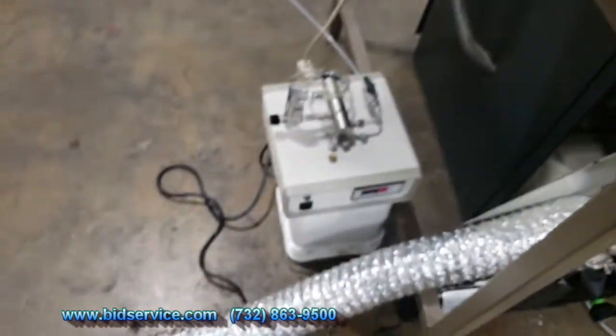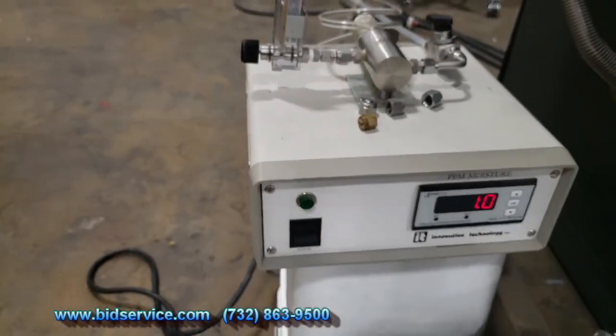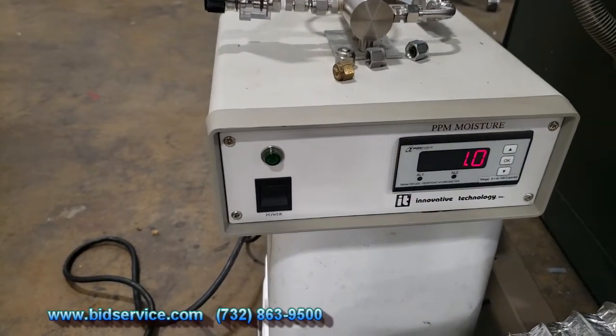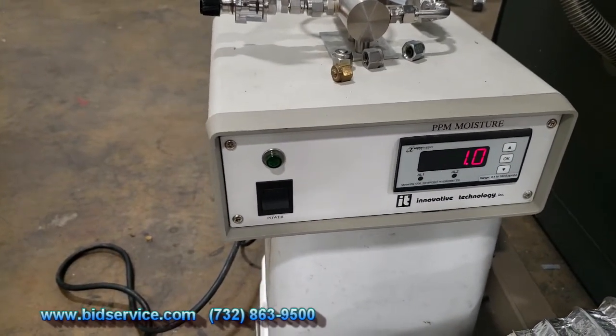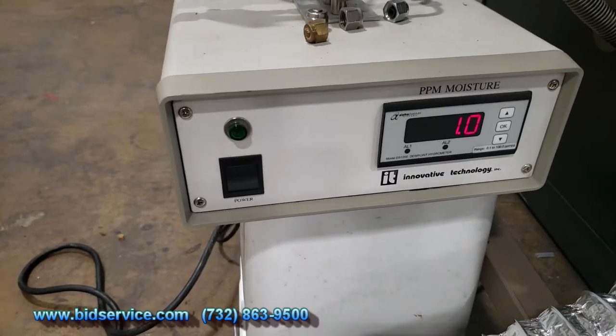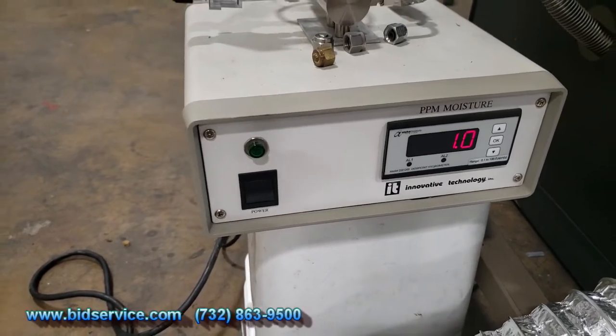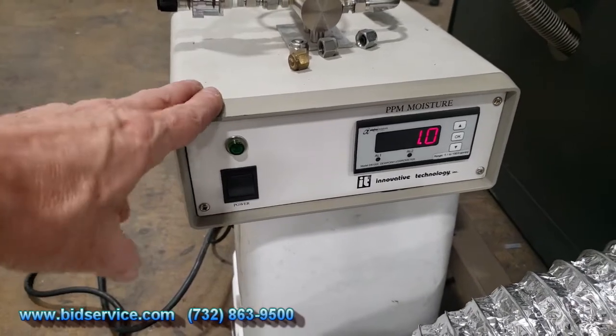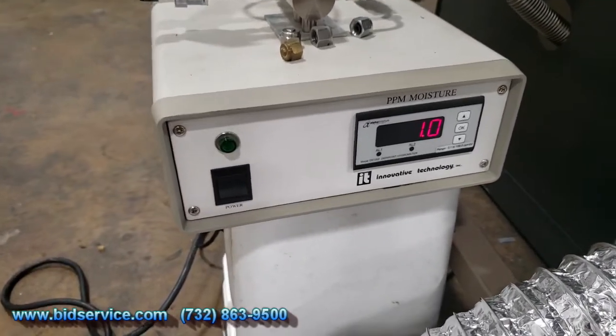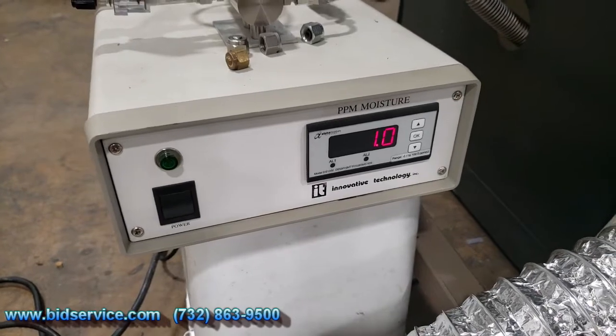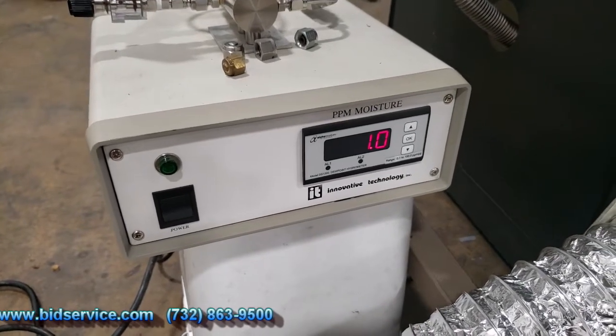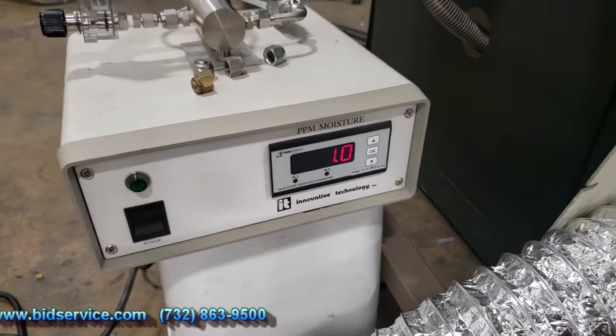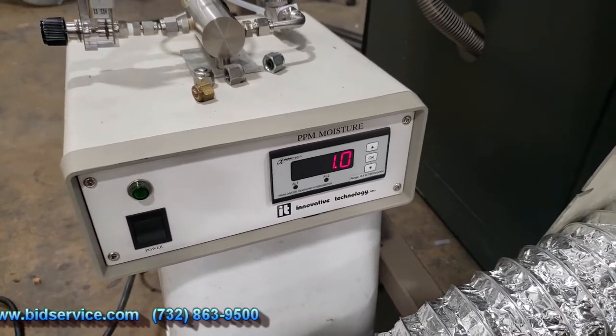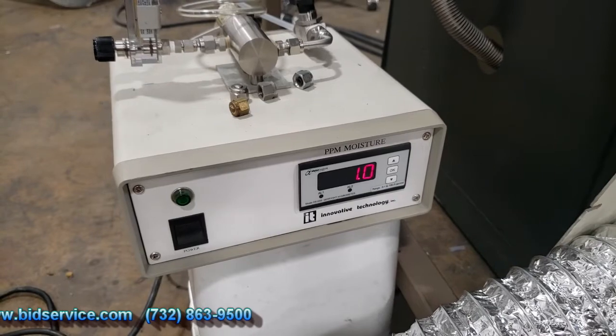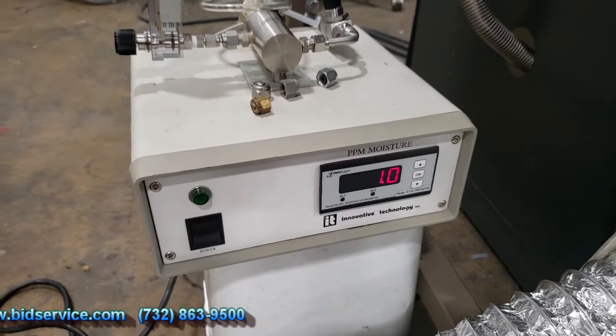So this will tell you what the moisture is inside. And as you can see, this gauge is valid between 0 and 100 parts per million of moisture, and right now we're sitting at 1.0. Again, this is our house unit. If you want to purchase your own, you need to put on your own moisture monitoring system. But here we're pulling 1.5 liters per minute out of the box and verifying that it does reach 1.0 parts per million.